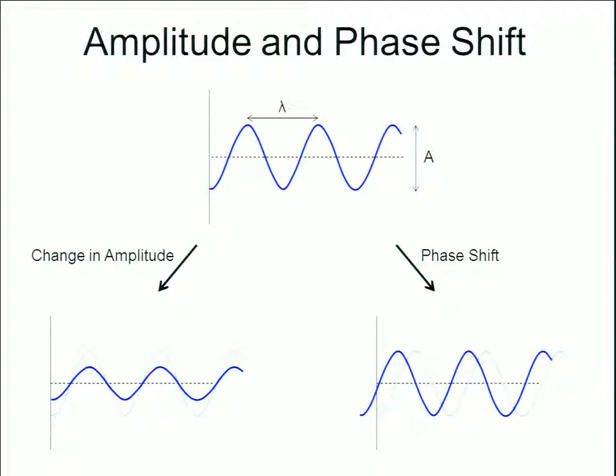Two types of information we can get: we drive the cantilever at its resonant frequency set point, and as we interact with the sample we can observe a change in amplitude, which provides information. We can also acquire phase shift data, which gives us different information as well.